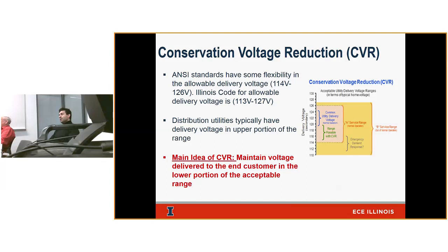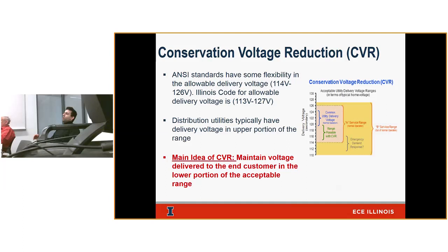Distribution utilities historically used to operate in the upper range of that voltage, mainly around 125 to 126. If you go to any of our substations and look at the voltage regulator or the LTC, they're most likely set at 125 as a setpoint with a bandwidth of plus or minus 1, so ranging from 124 to 126. The reason we do that relates to voltage drop calculations: on a distribution circuit, as you go farther from the substation, voltage tends to drop because of impedance. We want to make sure customers are nowhere near the lower end of the allowable range.